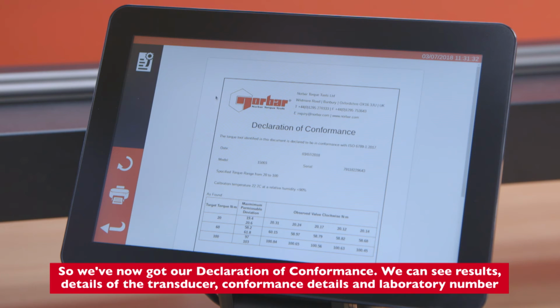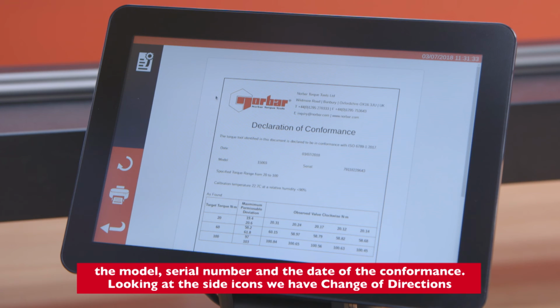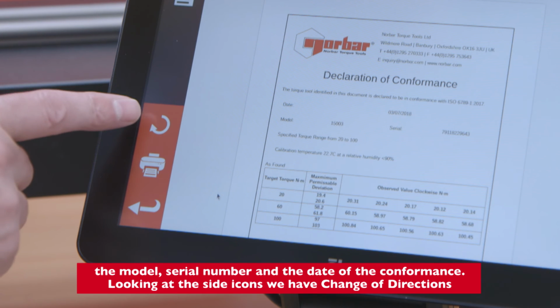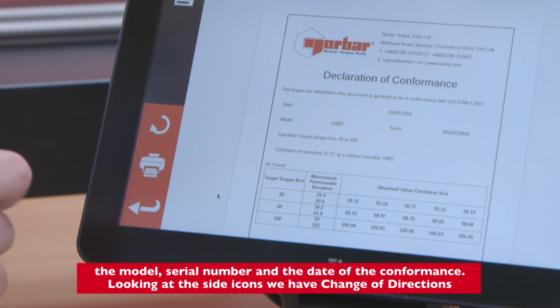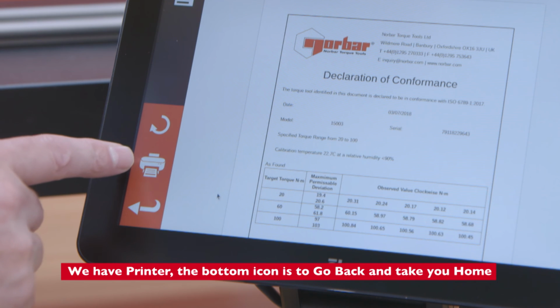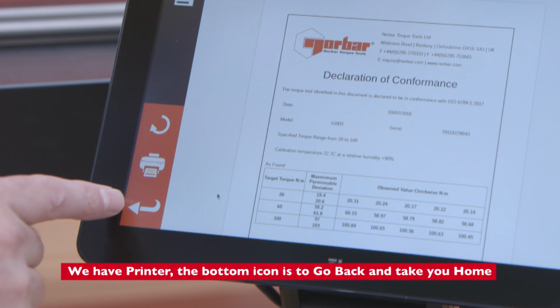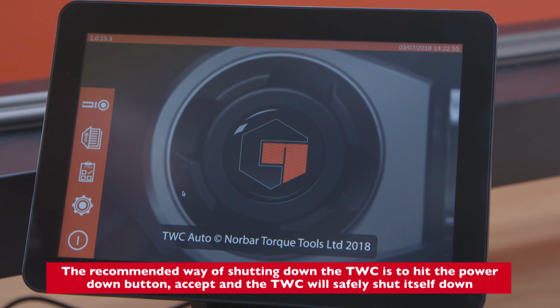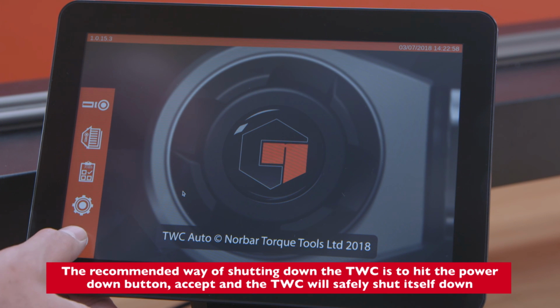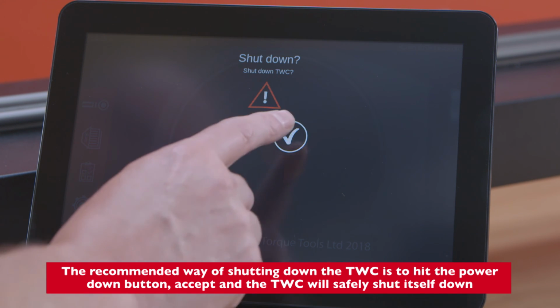So we've now got our declaration of conformance. We can see results, details of the transducer, conformance details and laboratory number, the model, serial number and the date of the conformance. Looking at the side icons, we have change of directions. We have printer. The bottom icon is to go back and take you home. The recommended way of shutting down the TWC is to hit the power down button, accept, and the TWC will safely shut itself down.